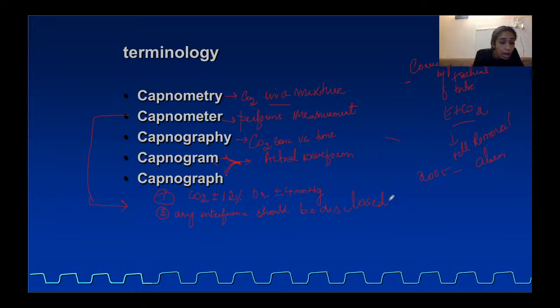It must have alarms for both high and low carbon dioxide, including inspired as well as expired carbon dioxide. Any interference should be disclosed by the manufacturer. And the carbon dioxide variability should be within plus or minus 4 millimeters of mercury. So these are the basic standards for capnometry.